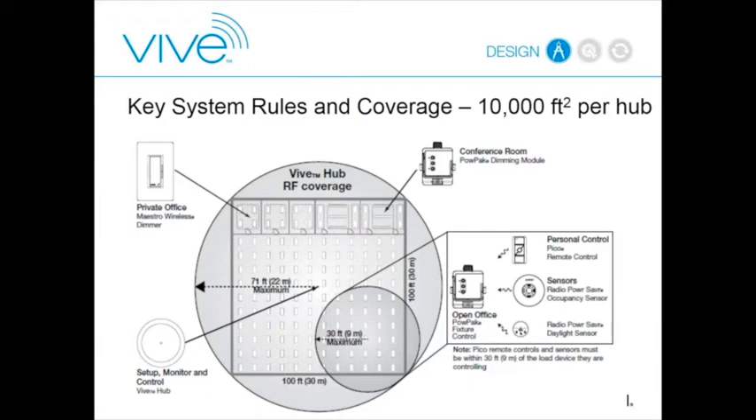The smaller circle in the diagram shows the range of a receiver—for example, a PowPak fixture controller or a Maestro. Each of those devices still has to be within 30 feet through construction material, or 60 feet line of sight, to all controls talking to it. So PICO wireless controls, occupancy sensors, and daylight sensors all still have to be within 30 or 60 feet of the load controlling device.